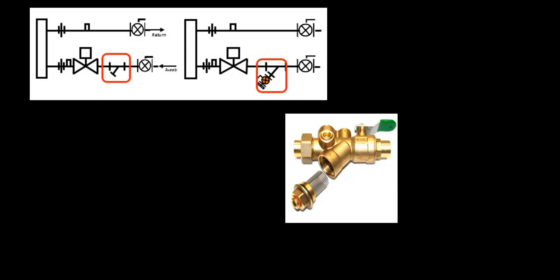So what we can see here is, in the red boxes, where it's located. It's always going to be on the supply line directly after the shutoff valve in between the building's connection. You can see that the strainer will always be installed just after the ball valve, which is just after the building's water supply connection point. We want the strainer to be the first component to see water flow before the water hits the other valve components and goes to the coil and exits the fan coil.